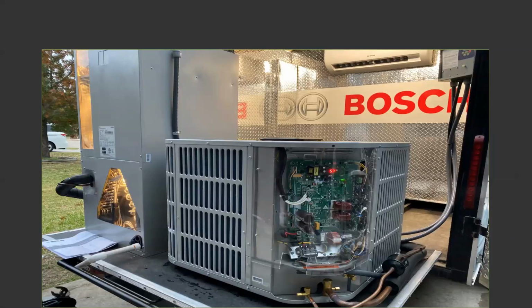So let's move over to the right, take a look at the condensing unit. This is the 3-ton condensing unit that James has in his trailer down in the Texas area. And you see that we've got some green lights on this particular unit. This means that the unit has electric to it, it's ready to go, and it's actually running. So the 57 represents that it is running, and it's got 57 hertz through it. If you're familiar with the 1.0, you would notice real quickly that the green LED lights on the 1.0 now are red. So hopefully you will be able to see that more easily in the direct sun.